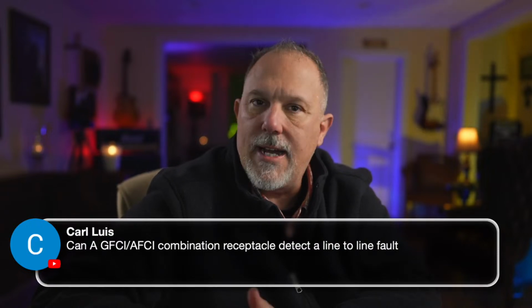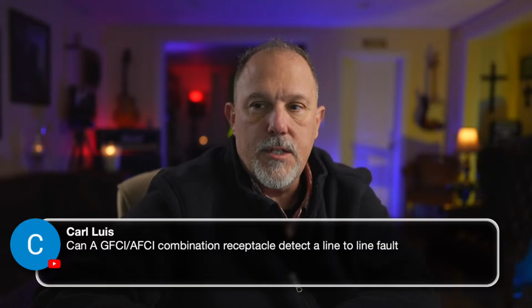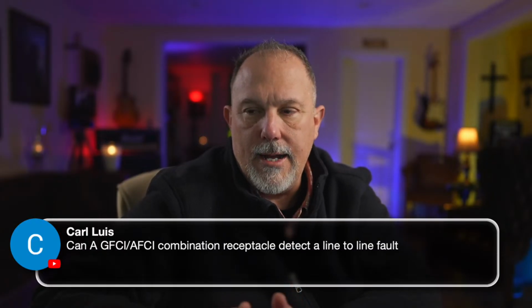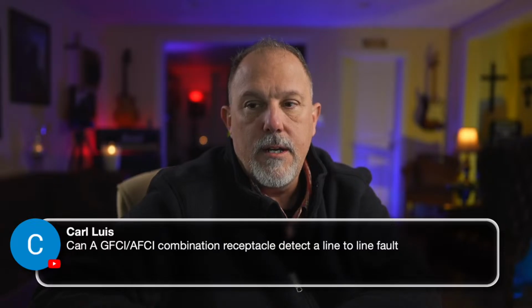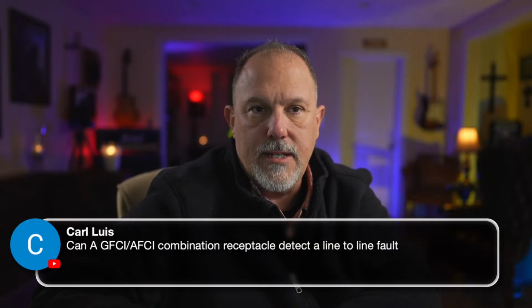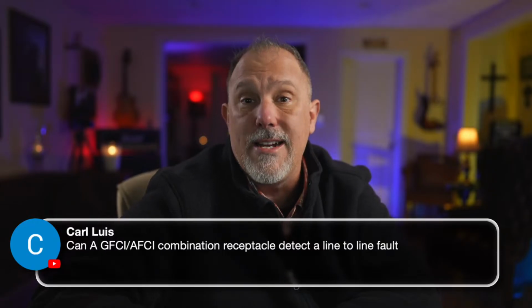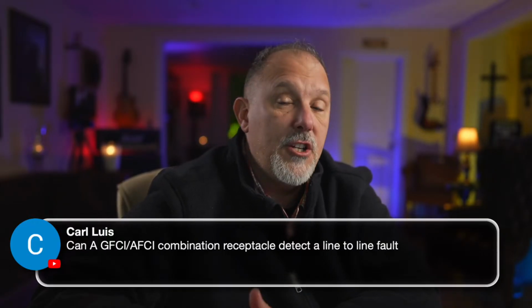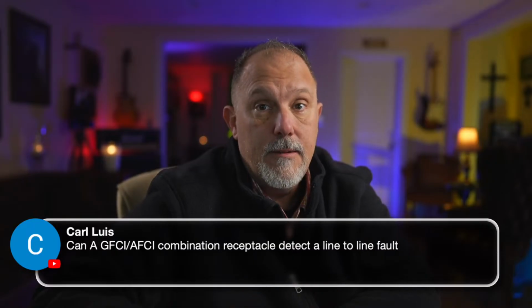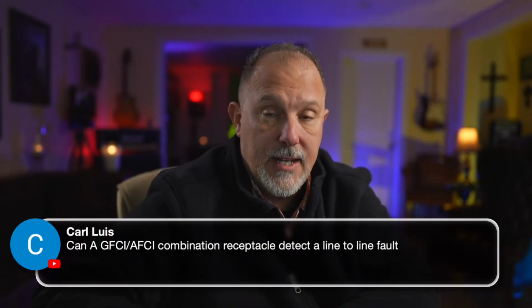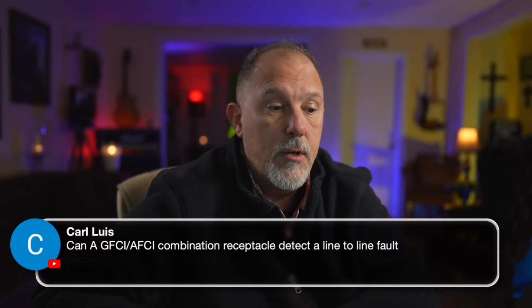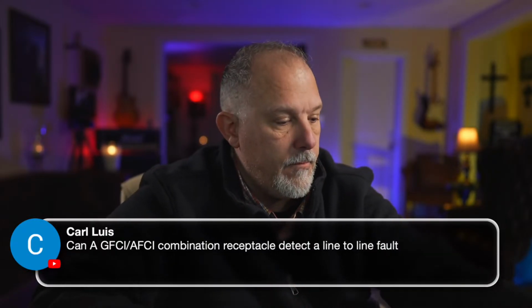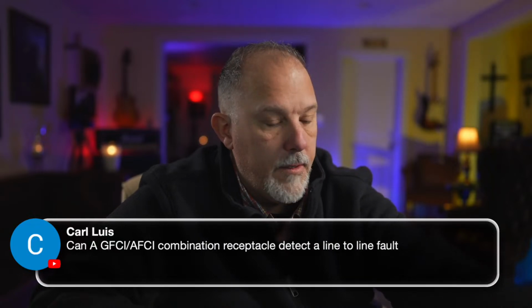So AFCIs are only going to detect an arc. If you do a line-to-line fault, that AFCI is not going to detect it. Plus, for me to have a line-to-line, that would have to be a shared neutral application, right? So I'd have to have a two-pole AFCI, and it would have to be a shared neutral application. All right. Carl, thanks for joining in. That's the first time I've seen your name in here. So good question. Thank you.